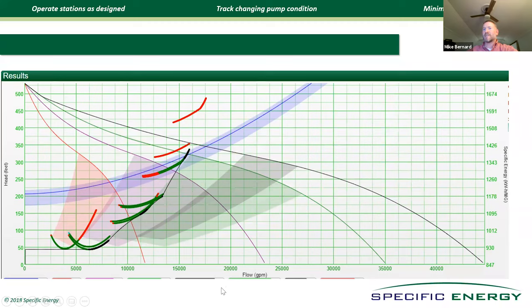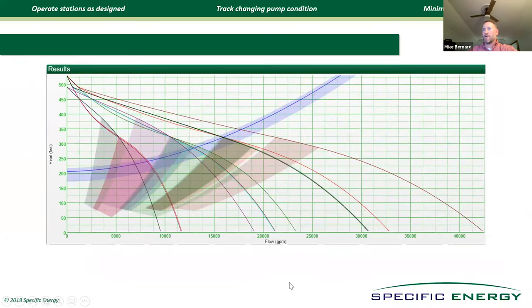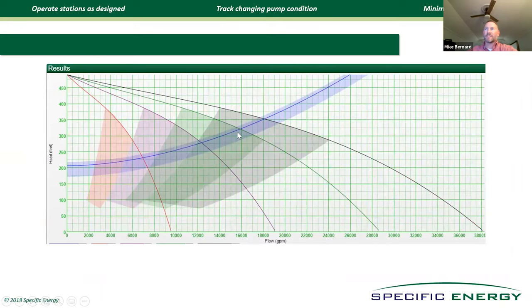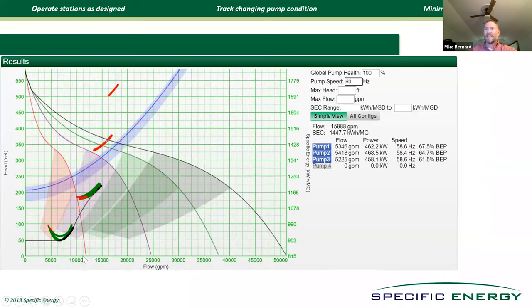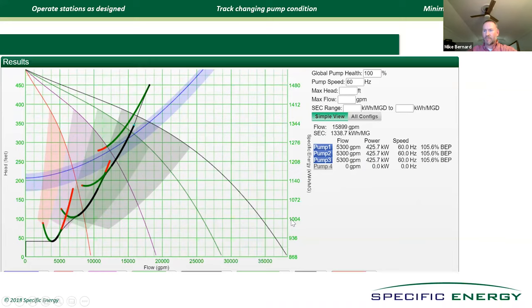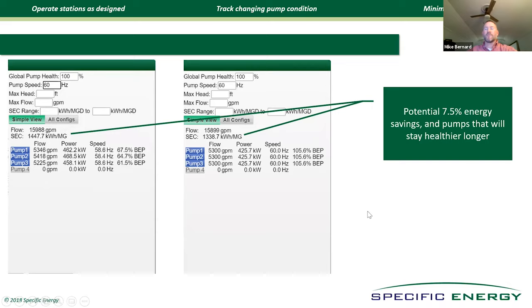What we intend to do is as the other pumps fail, we won't replace them in kind. We'll find a better pump like this CLC, and we'll go from here to here to here to here, and eventually we'll have all four pumps and you see that there's no gaps here. I can go all the way from 2,500 gallons a minute. If I want to run all four pumps, I can get as much as 18,000 gallons a minute, and I give the DPO somewhere to operate. So my specific energy map goes from here to here, and this is what we want to see is this overlap where there's a possibility of finding a solution anywhere along the specific energy map. A much bigger deal as well is that there's a potential energy savings which is more than going to pay for the installation of the DPO and the design of the additional pump. We love to do things like this. We love to train people on how to both design and operate their systems better.